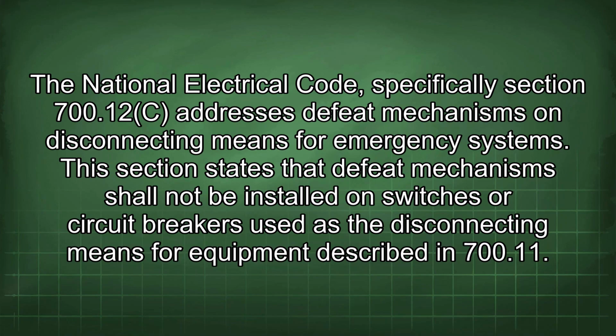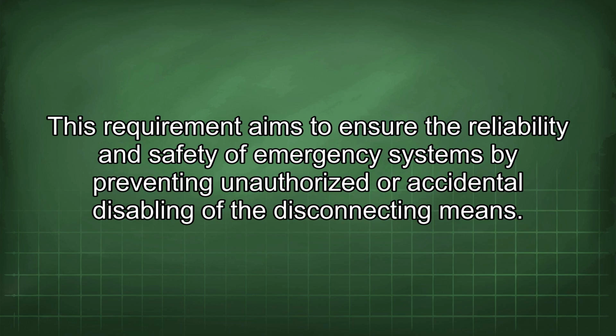The National Electrical Code, specifically Section 700.12(C), addresses defeat mechanisms on disconnecting means for emergency systems. This section states that defeat mechanisms shall not be installed on switches or circuit breakers used as the disconnecting means for equipment described in 700.11.